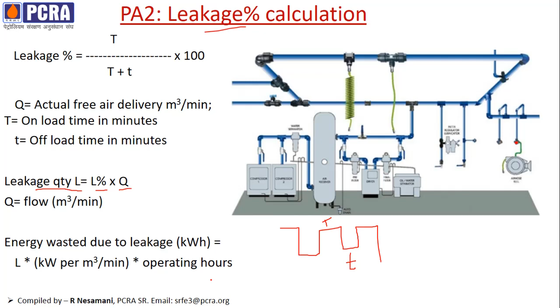So we have to calculate how much energy we are wasting due to leakage. Its formula is the leakage quantity multiplied by the power, which we have to measure using a power analyzer, multiplied by the operating hours, which will give kilowatt hours. This can be converted into energy cost by multiplying with the energy tariff.